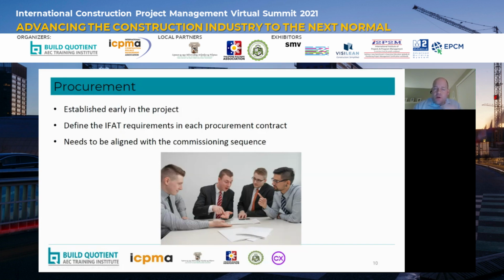In procurement contracts, your integrated factory acceptance test requirements need to be defined: what you want the manufacturer to execute in the factory before the equipment leaves and goes to site. So when putting together procurement contracts, you need to consider all the technical impacts and requirements for IFAT up front, so the manufacturer proceeds with testing in the factory as required to de-risk the project.